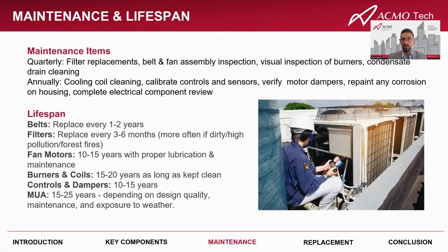Maintenance is extremely important for these machines. There are monthly, quarterly, and annual tasks that need to be done. For example, filters should be replaced every 3 to 6 months. Belts and fans should be checked quarterly, and motors can last 10 to 15 years if lubricated and maintained. If ignored, this would lead to breakdowns, higher costs, and poor indoor air quality.